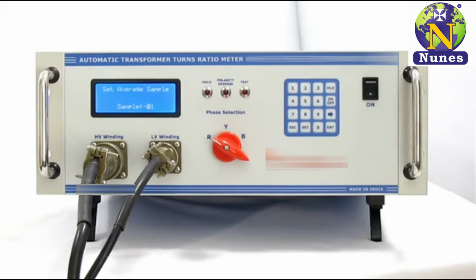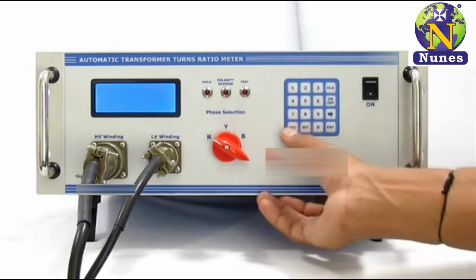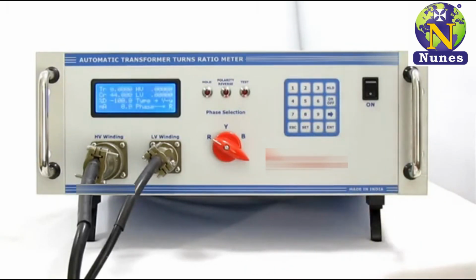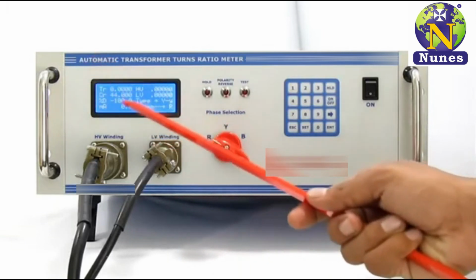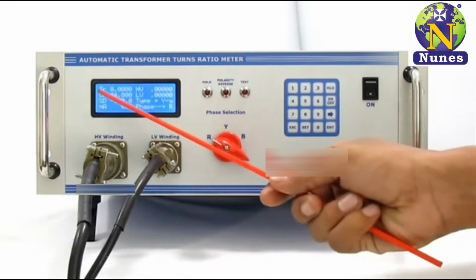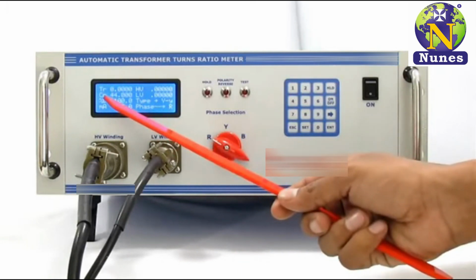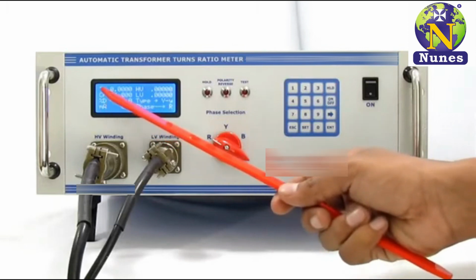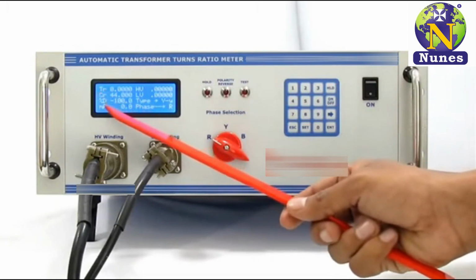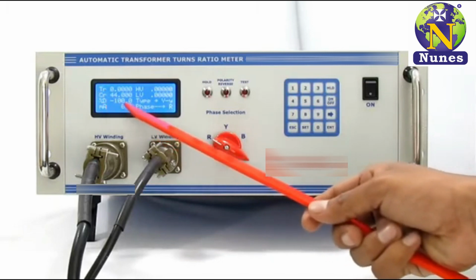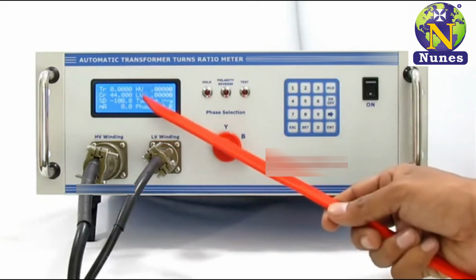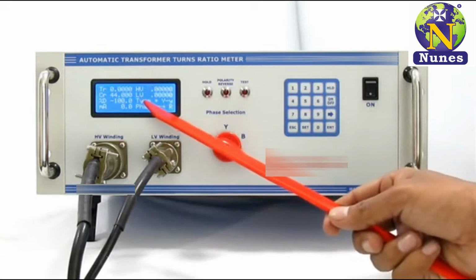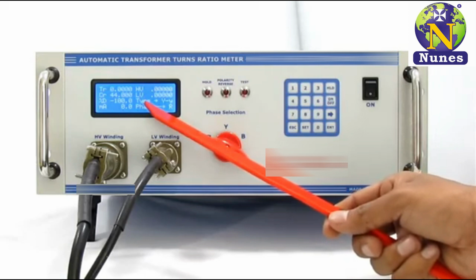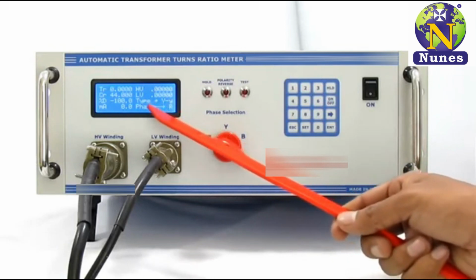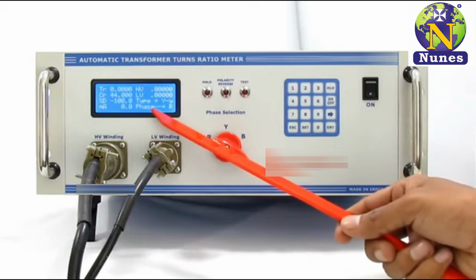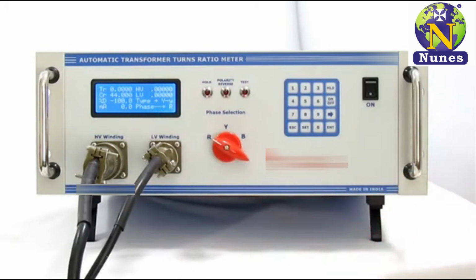Step 9. Now press the escape key to exit and to start measurement. Here you can see all parameters in the display. TR is measured turns ratio in 5 digits, CR is calculative ratio, percentage D is percentage deviation between measured and calculative ratio. Milliampere is excitation current in milliamps, HV is high voltage side applied voltage, LV is low voltage side measured voltage. Type is transformer type, star or delta star for distribution transformer. And selected phase is for the selected phase of the transformer for measurement of ratio.